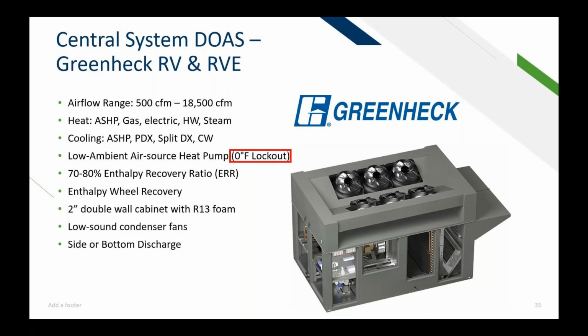0 degrees. In most cases, you can get 70 to 80% enthalpy recovery ratio, which you need above 70% enthalpy recovery ratio for stretch code. That's from an enthalpy wheel. And you get really great construction from Greenheck, the 2-inch double wall cabinet with R13 foam. Always low sound condenser fans, and you can do side or bottom discharge.